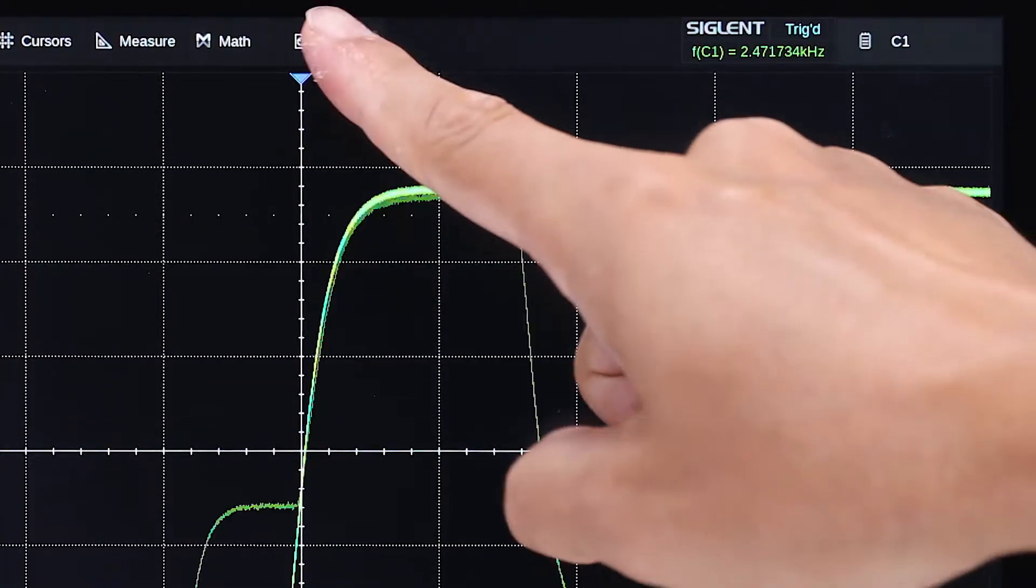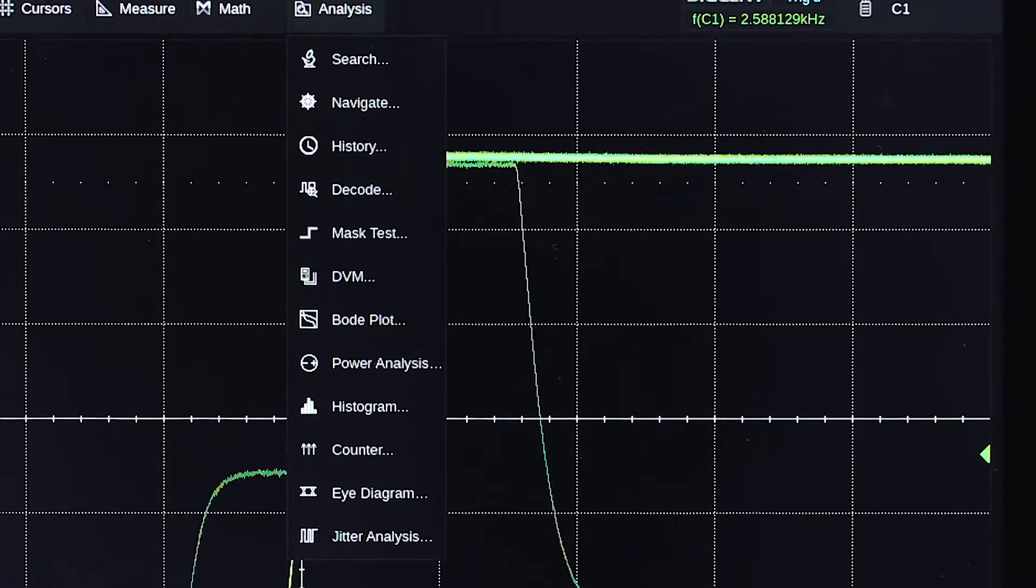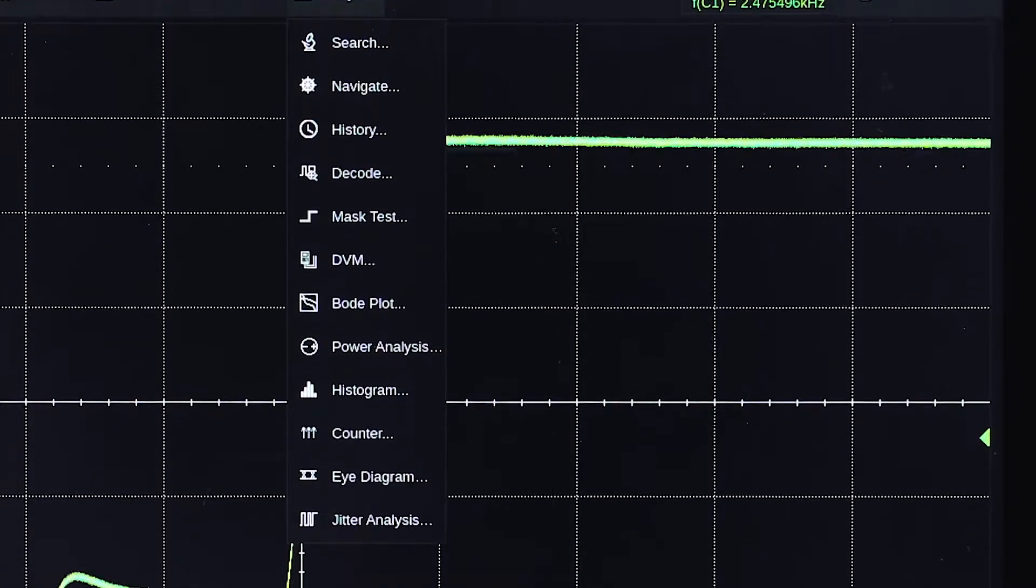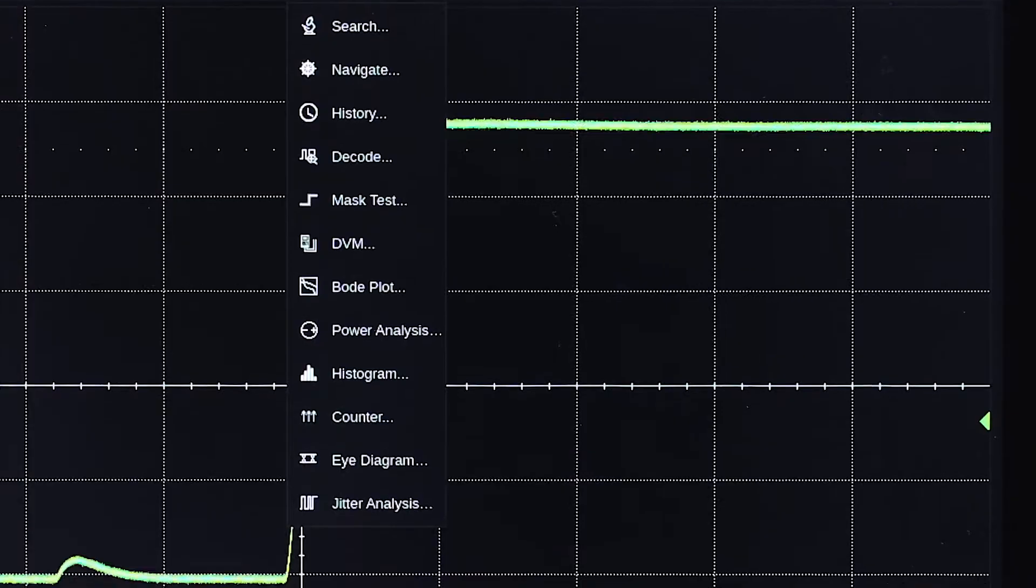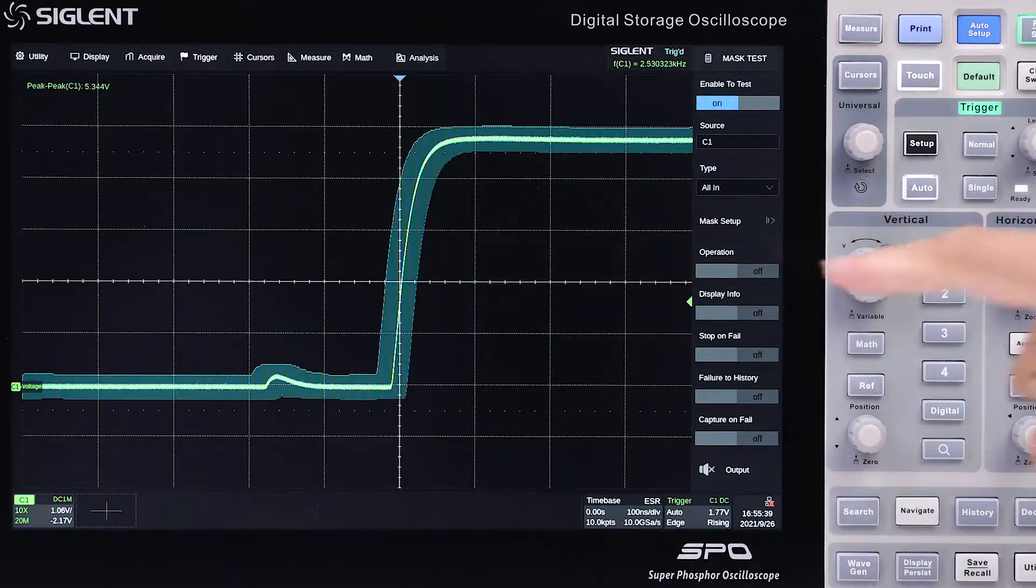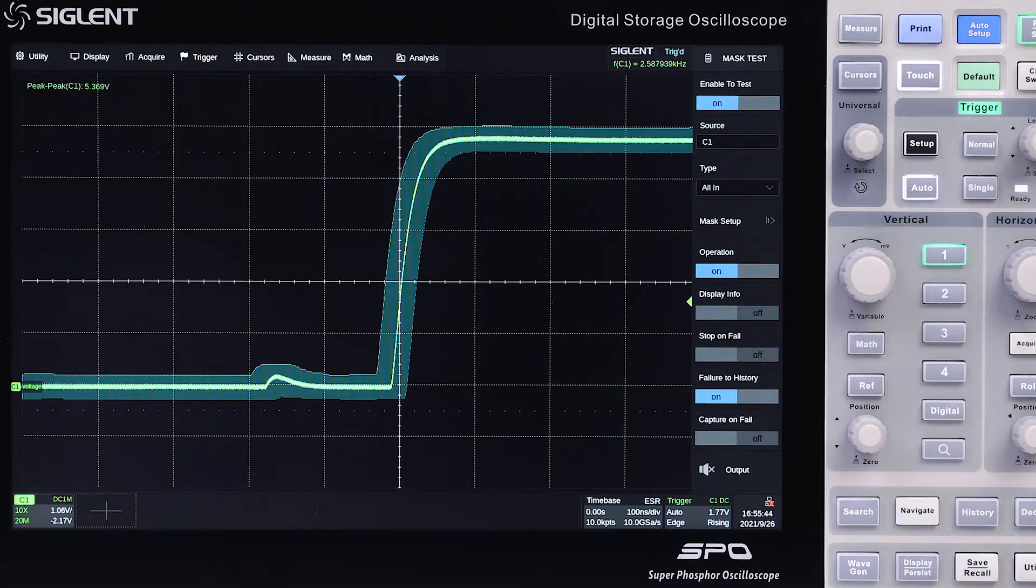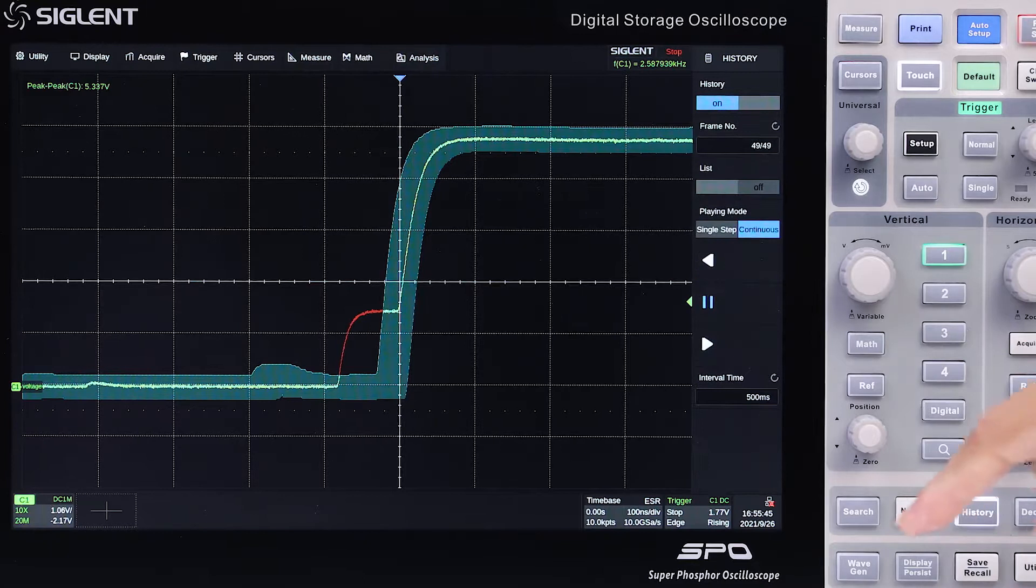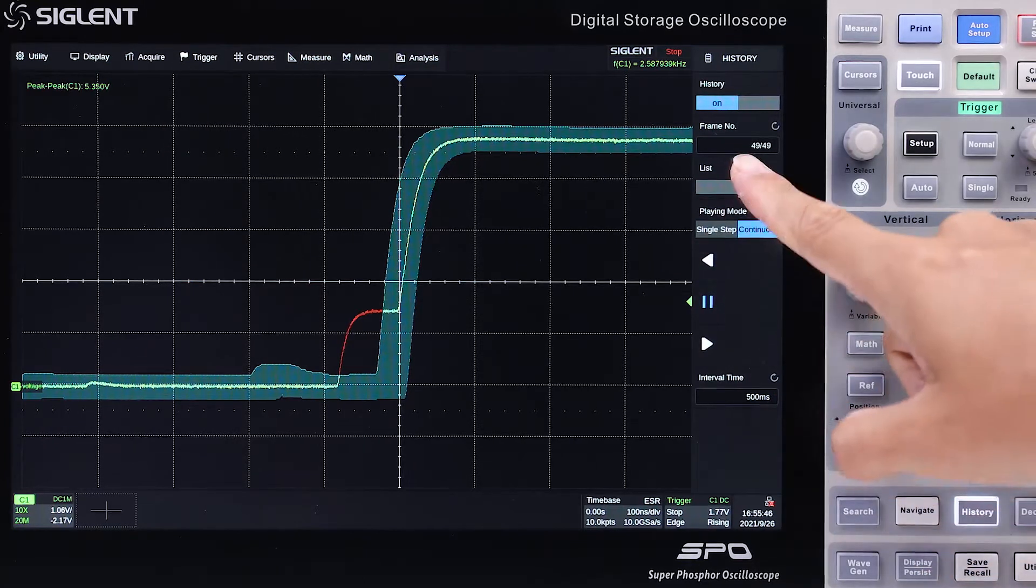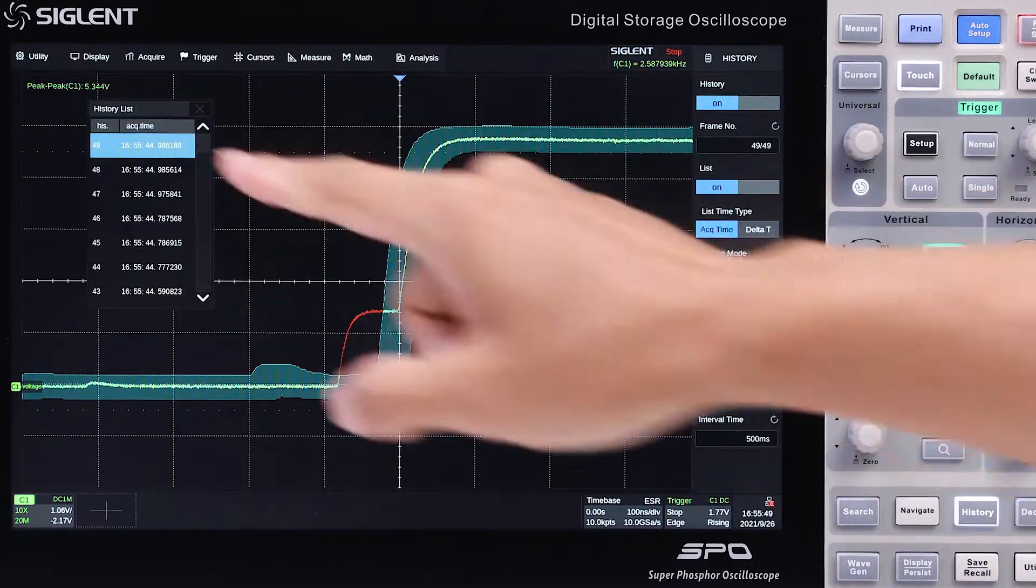Twelve different analysis tools can be accessed quickly using the top menu. Pass-fail frames can also be stored in history, and the hardware-based mask test can evaluate up to 18,000 trigger events per second.